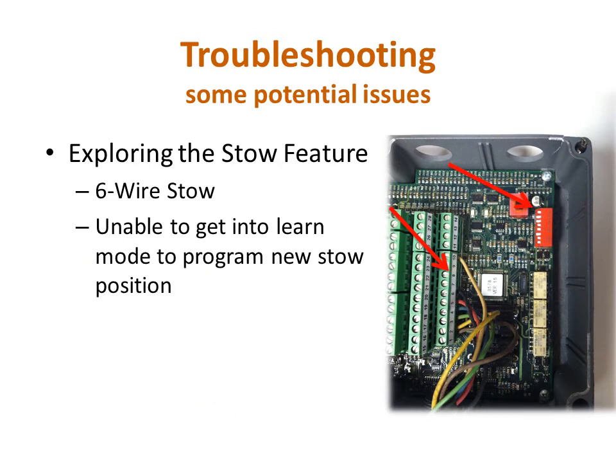There are several reasons why the monitor will not go into Learn mode. One of those is the presence of a 6-wire Stow controller. That isn't to say that you can't get into Learn mode with this controller, just be aware that it requires some adjustments to be made. I won't go into those here, but there are detailed instructions in the StreamMaster operating instructions available on the Akron Brass website. Additionally, if dip switch 2 is up, the monitor will not enter Learn mode. Likewise, the position of dip switch 8 is important since its function is to enable or disable Learn mode.